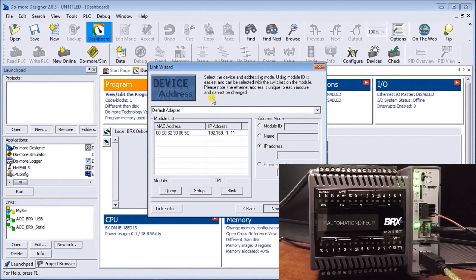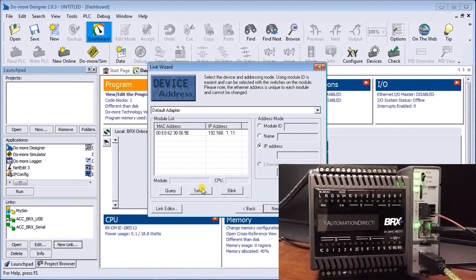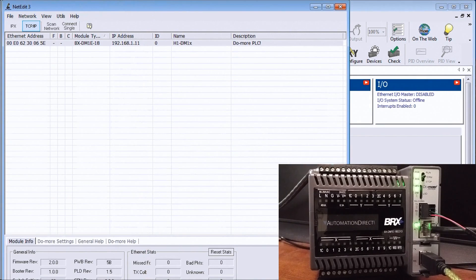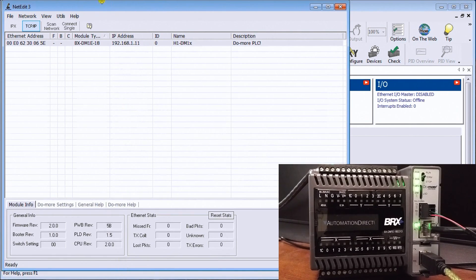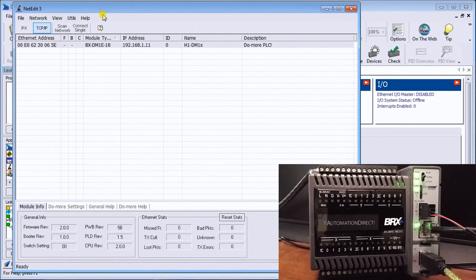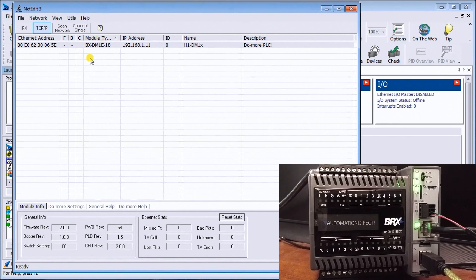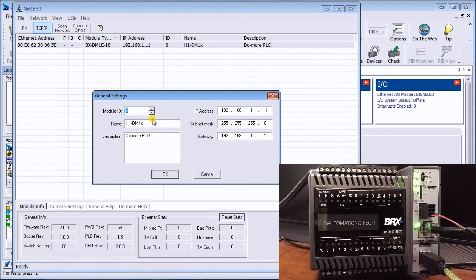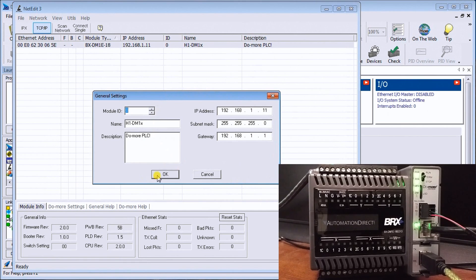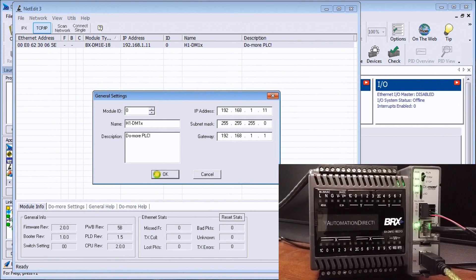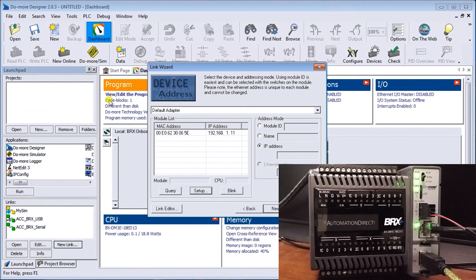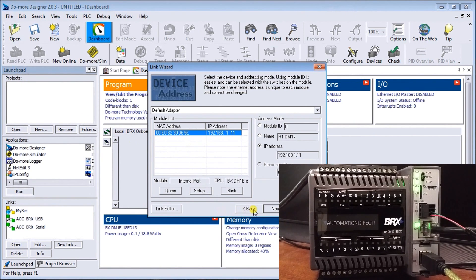Now it looks for information. If we didn't see this up here—remember we already preset it when we're connected with the USB—but if we did not, we hit setup. That will call up another program called Net Edit 3, which goes out and looks for all of the controllers that are on the system. If we didn't have the IP address set, we could double-click on here and it allows us to change our values in the controller while we're online.